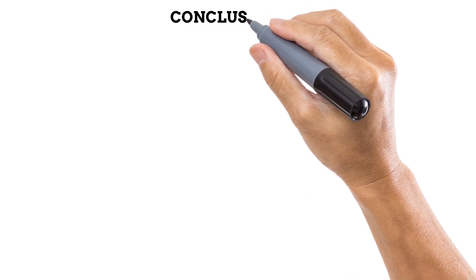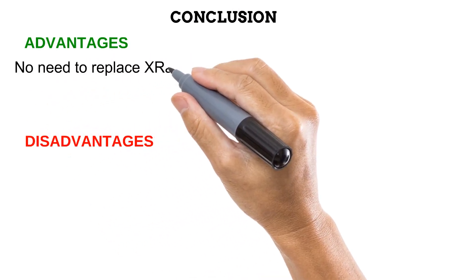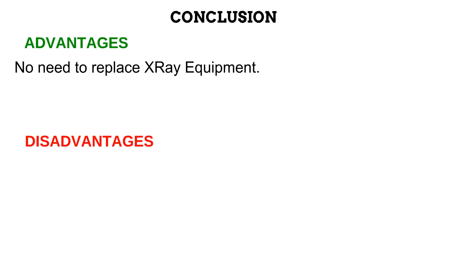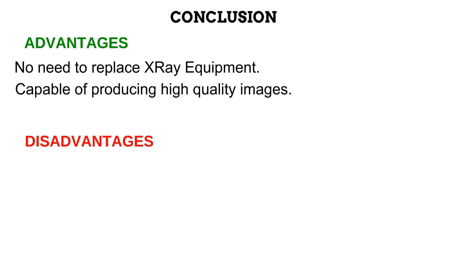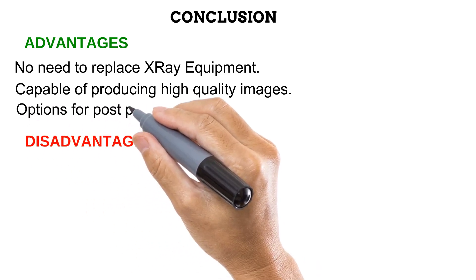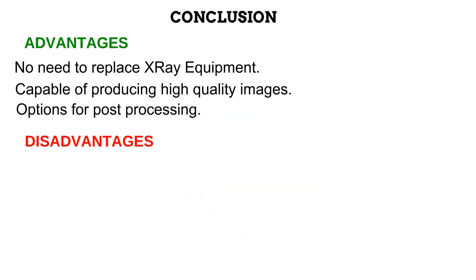Now that we have looked at how images are acquired in computed radiography, let us look at some advantages and disadvantages of this imaging system. As you may have noticed, there is no need to replace equipment like the x-ray tube, table, and bucky when an upgrade is being made from film screen to computed radiography, because the cassettes used in computed radiography are designed to fit into these equipment like film screen radiography cassettes. Secondly, computed radiography systems have an inherent ability to produce high-quality images. Also, computed radiography provides options for manipulating certain features of the image after it has been acquired, which helps to reduce the number of repeats that need to be made.